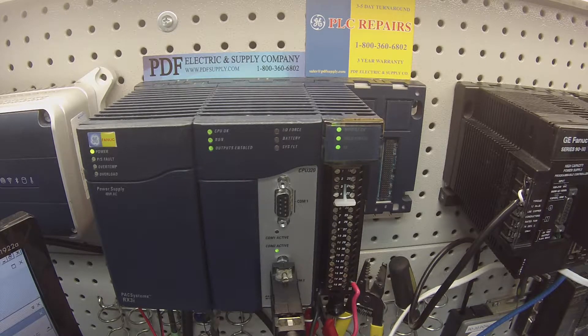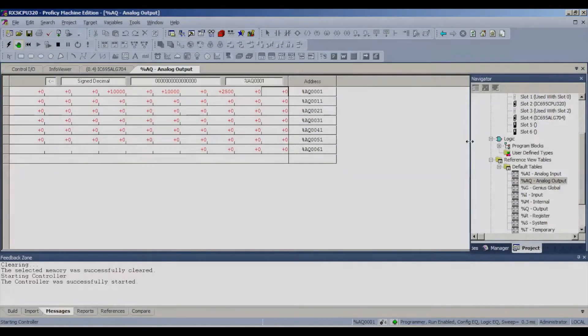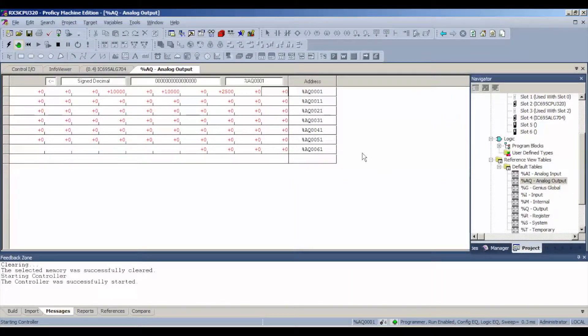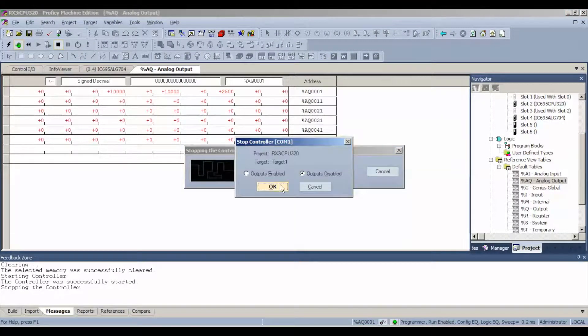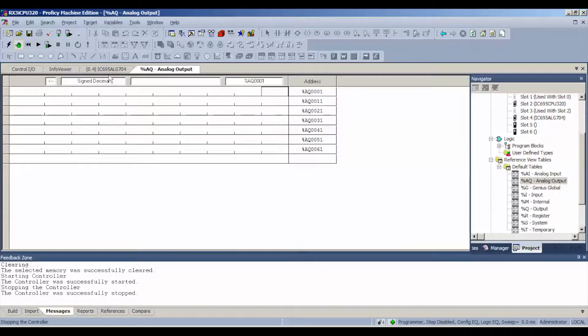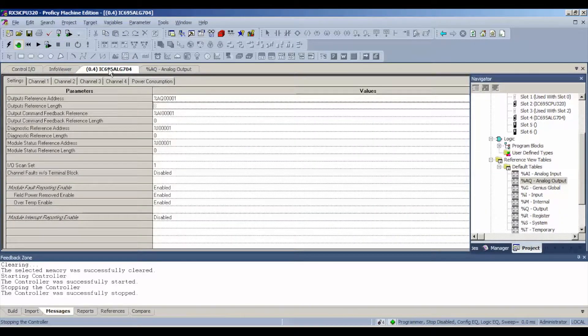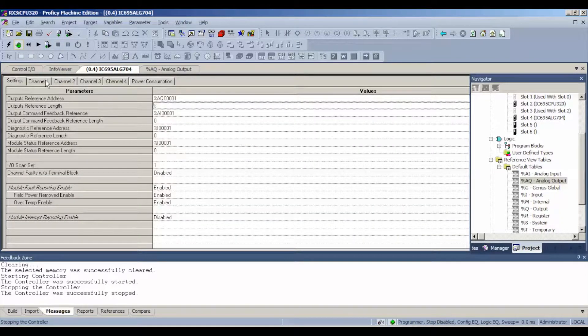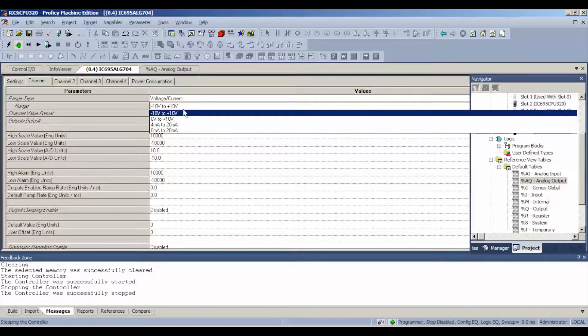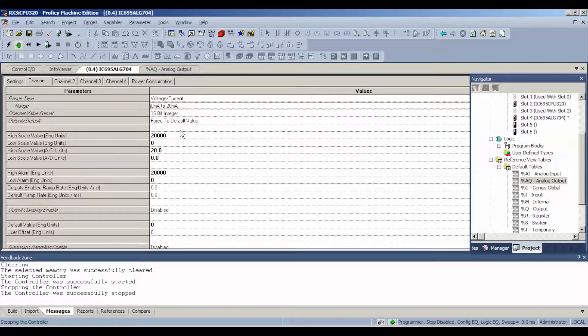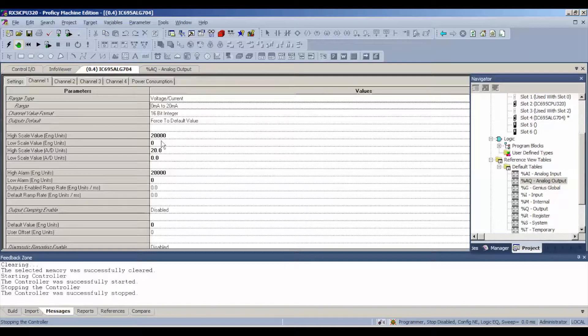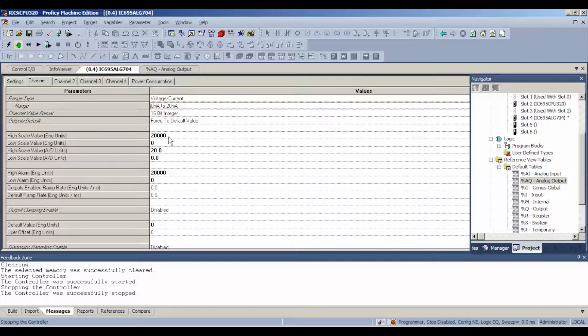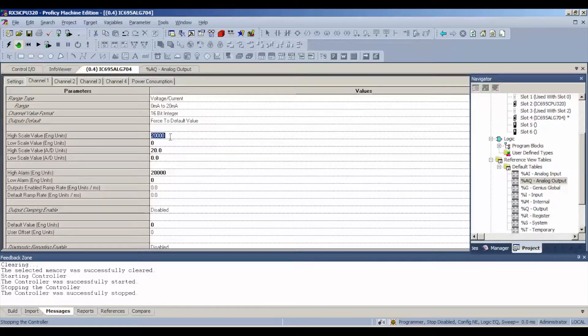So now that we've tested voltage, we're going to stop the controller. We're going to go into our ALG704 tab, channel 1, and we're going to bring it to 0 to 20 milliamps is fine. Note that our scale values have changed. Our maximum value is 20,000. I'm going to show you when that's going to become important.